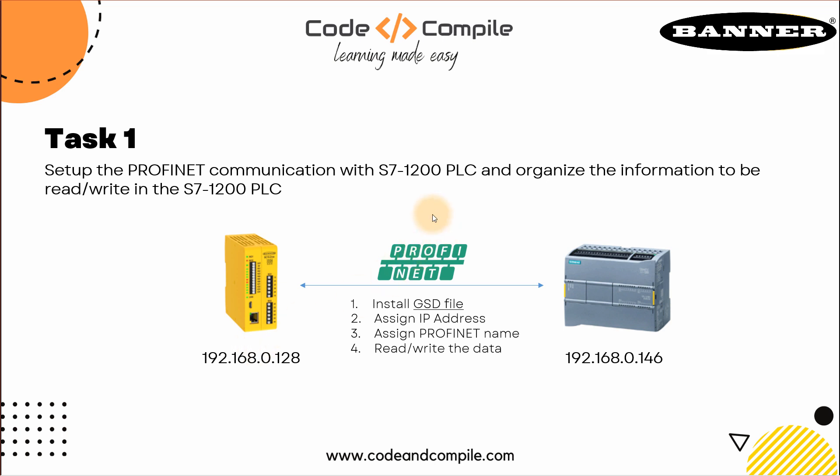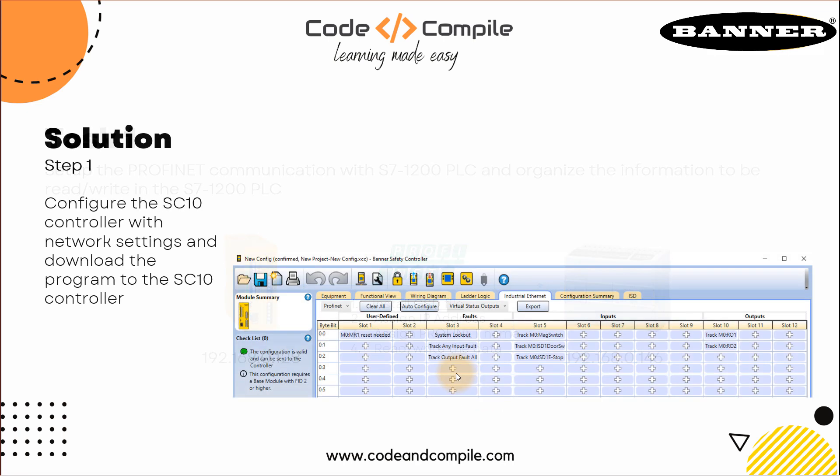The important fact is you need to install a GSD file, which you can find on the Banner Engineering website. The link I can provide in the resources. GSD file will help Siemens PLC to recognize the hardware. It's like a hardware catalog you need to know from the device. Then you need to assign the IP address, PROFINET name and start read-writing the data.